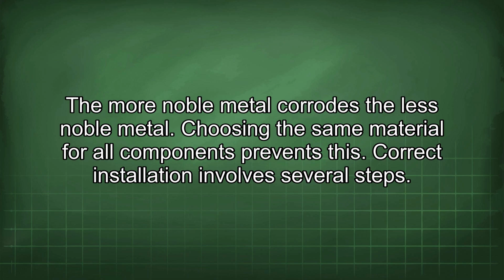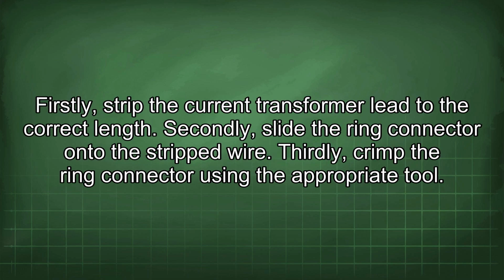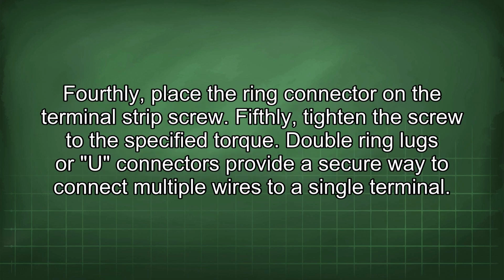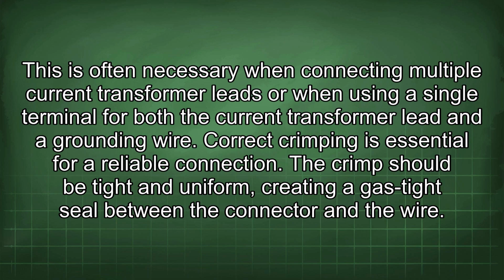Correct installation involves several steps. Firstly, strip the current transformer lead to the correct length. Secondly, slide the ring connector onto the stripped wire. Thirdly, crimp the ring connector using the appropriate tool. Fourthly, place the ring connector on the terminal strip screw. Fifthly, tighten the screw to the specified torque. Double ring lugs or U-connectors provide a secure way to connect multiple wires to a single terminal. This is often necessary when connecting multiple current transformer leads or when using a single terminal for both the current transformer lead and a grounding wire.